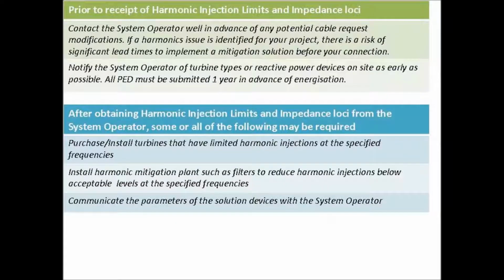So you give that then to your filter designer and they'll be able to use it to design a filter if you need to. Or you could just pick wind turbines that will be compliant. So back to what most customers do. This is the before, so after. So after obtaining these limits and loci, you then have to either purchase and install turbines that will be limited to those, so that you don't go beyond it. So your turbines might be able to do it on board. Otherwise, you'll have to install something like a filter to try and stay below those levels. And once you have decided what you're going to do, come back and talk to the system operator, because these things can interact with neighbours and it's worthwhile just checking that everything is okay. So if 2 people in a subgroup decide to get the same turbines, you could end up with new issues or whatever. So it's worth coming back and discussing.